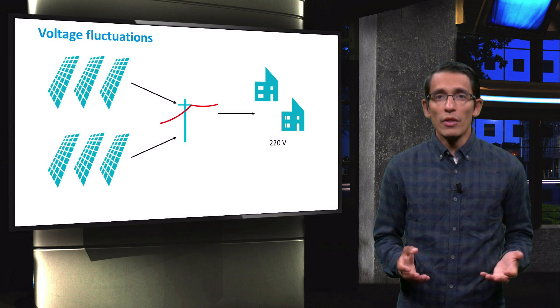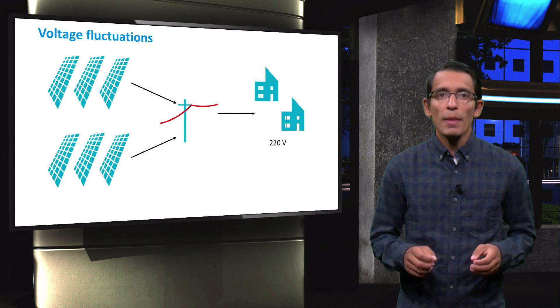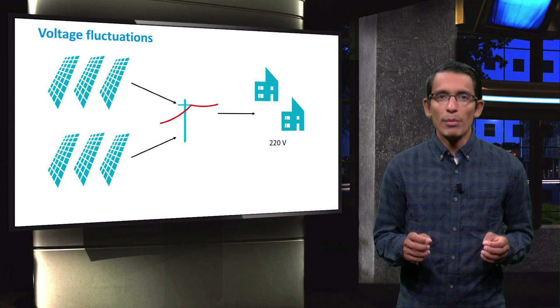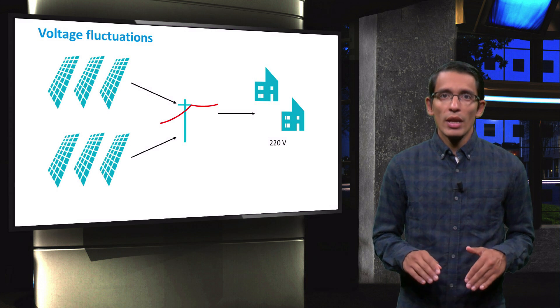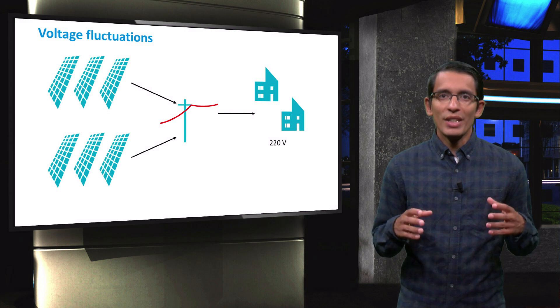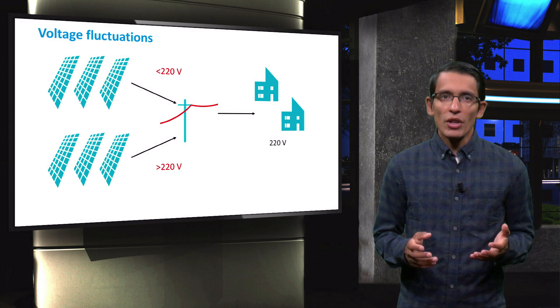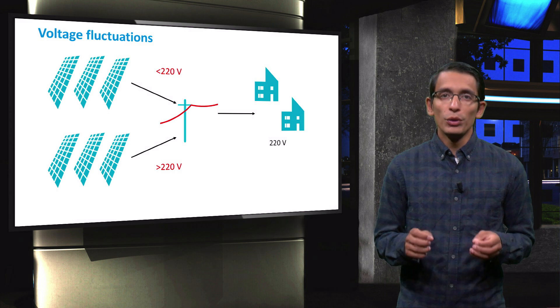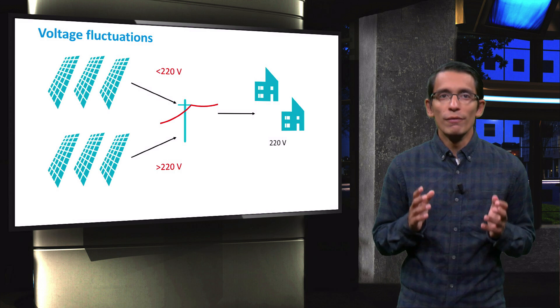On the other hand, in distributed generation technologies like photovoltaics, the power output is more variable and impossible to control. This can cause over voltage or voltage dip situations in the low voltage distribution system, which can have effects on the performance of different loads. Effects on the loads are usually noticed when the voltage fluctuates more than 10% above or below the nominal voltage.